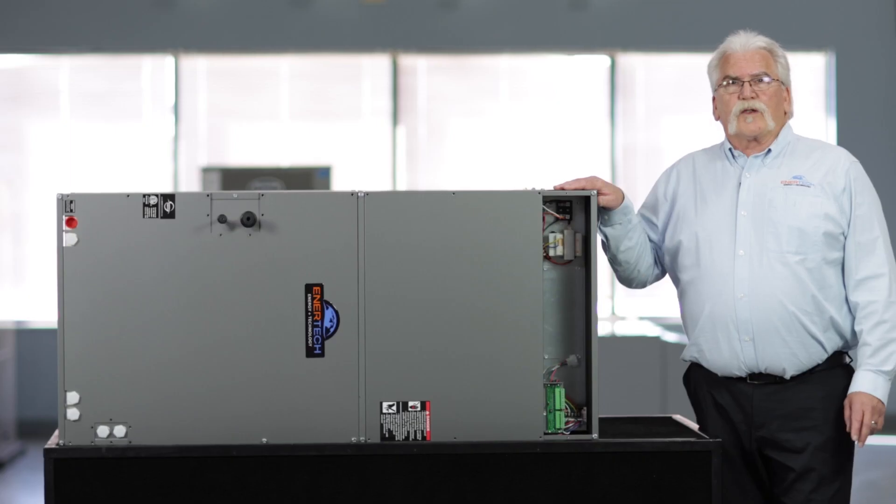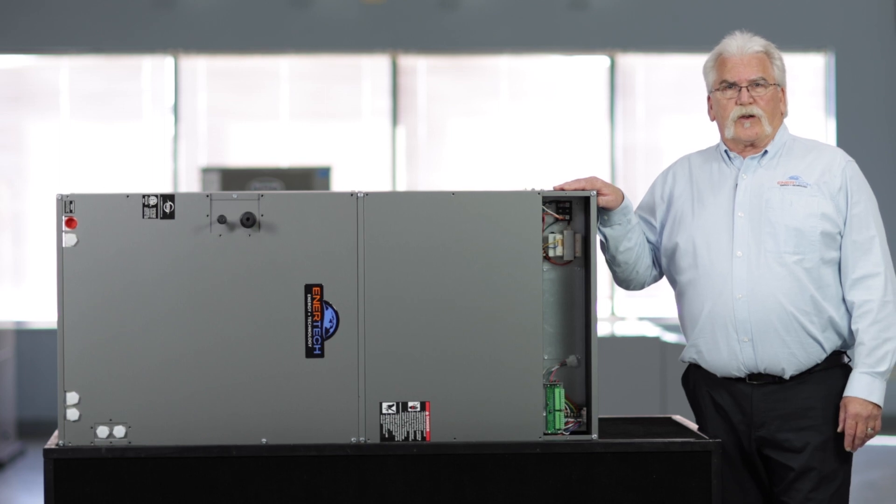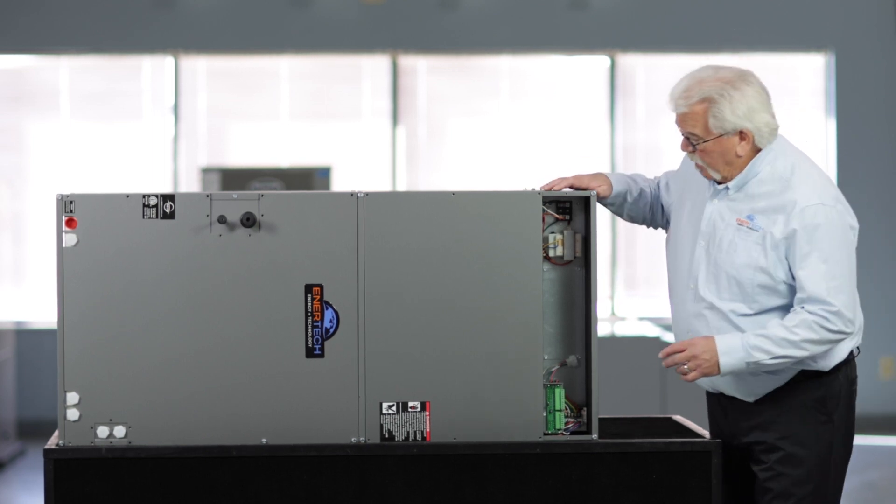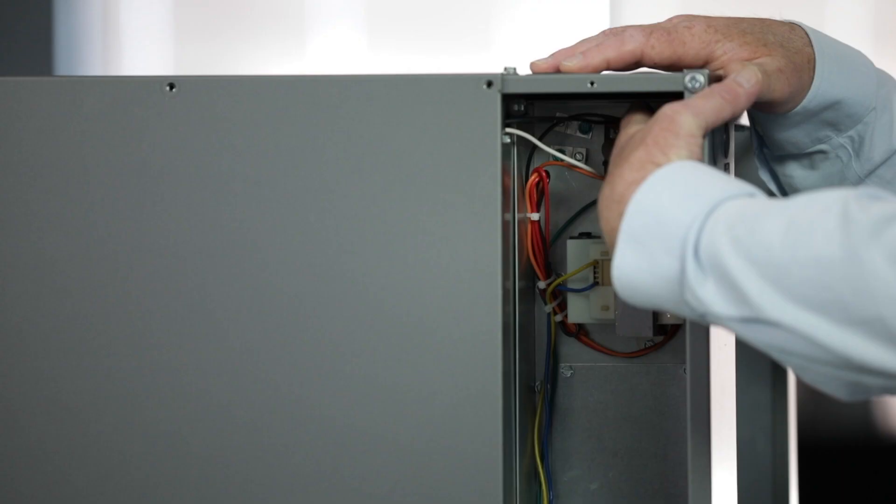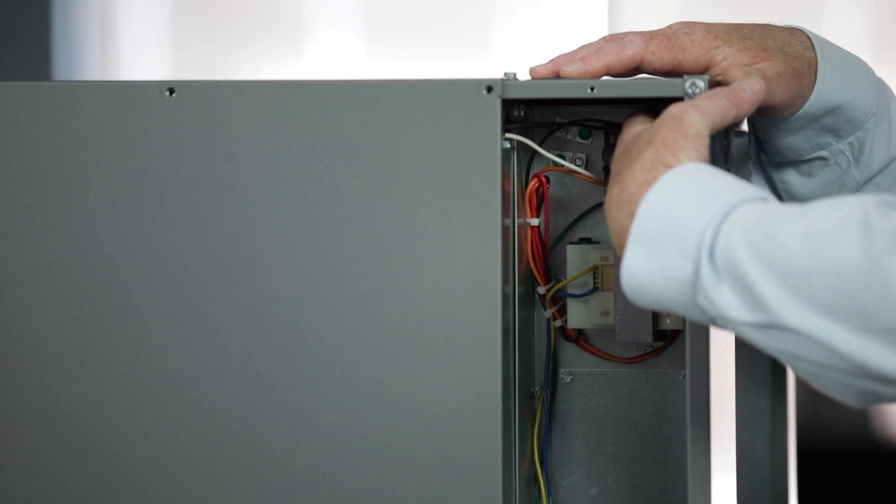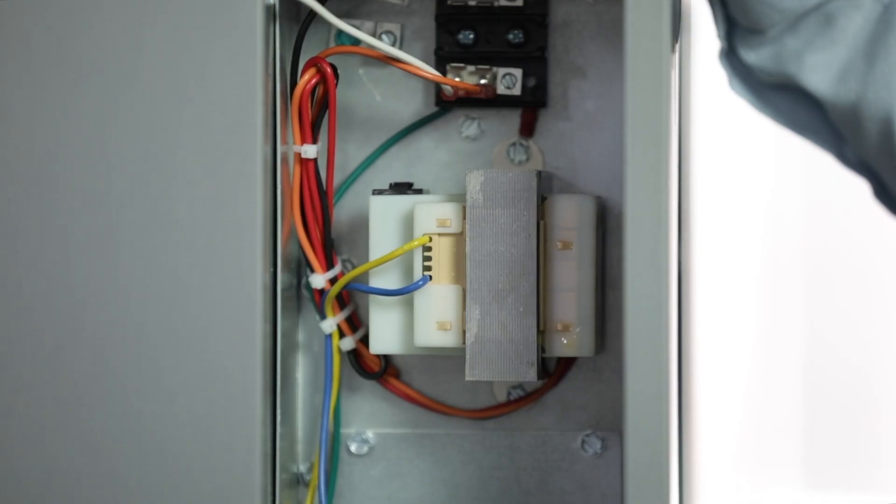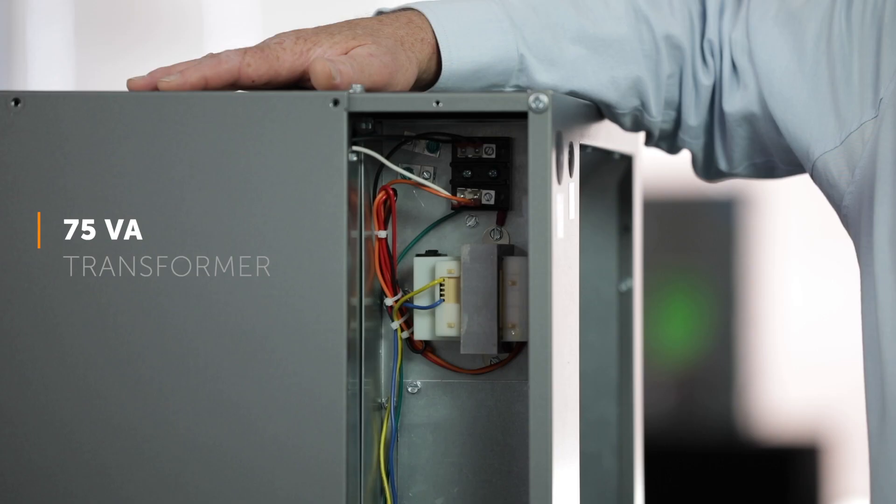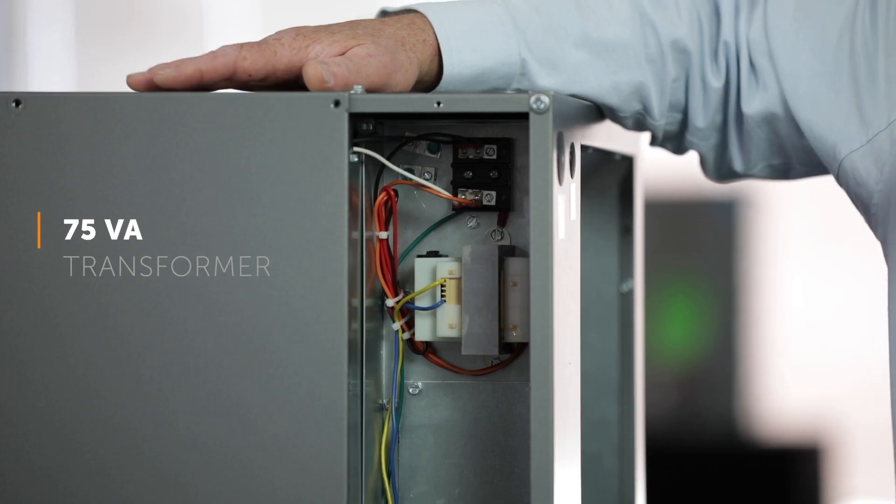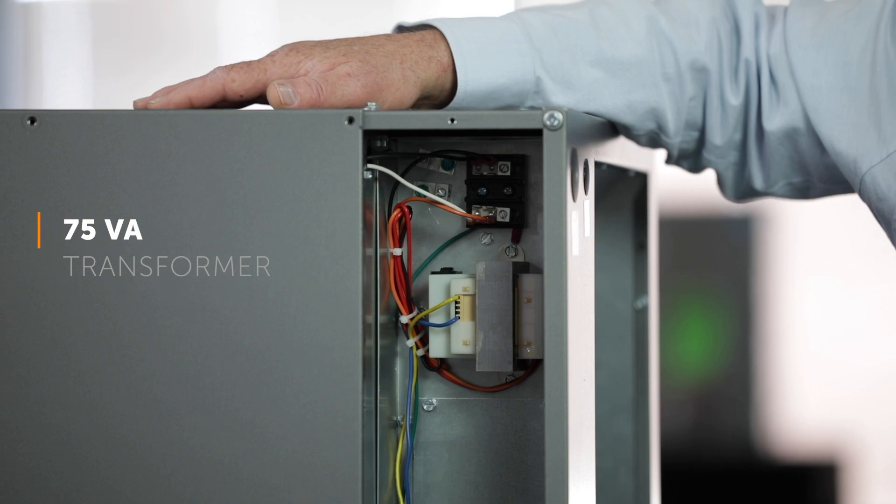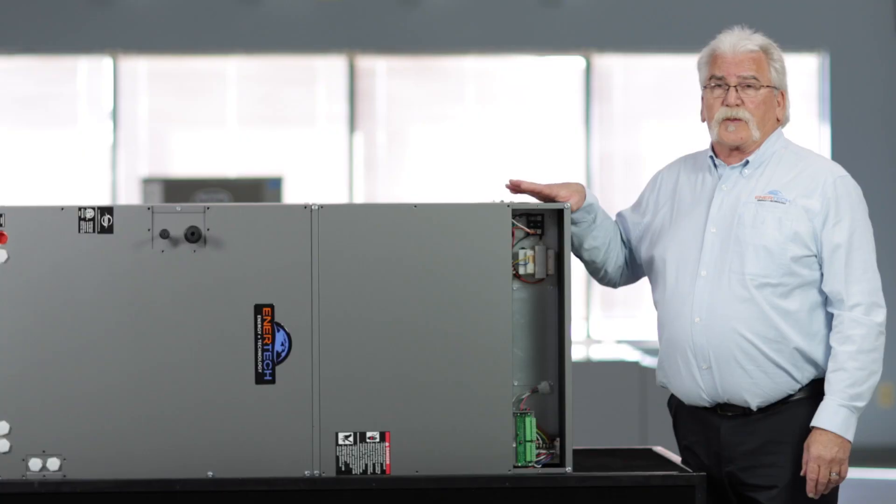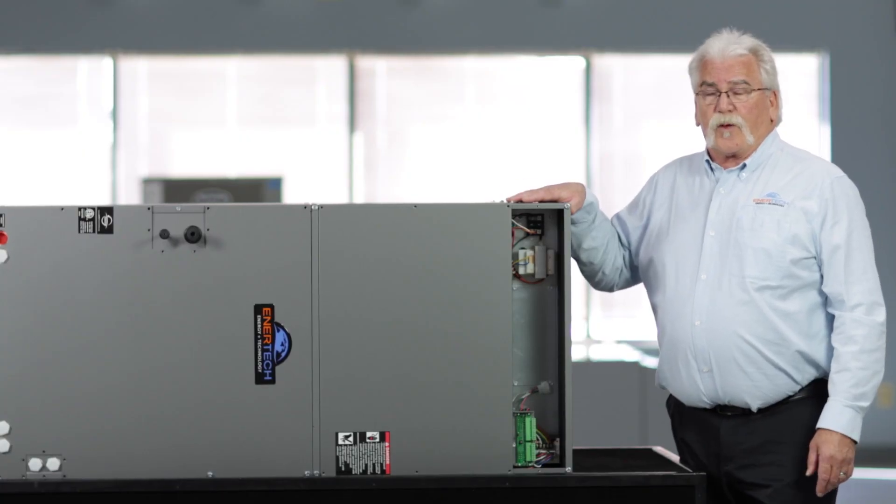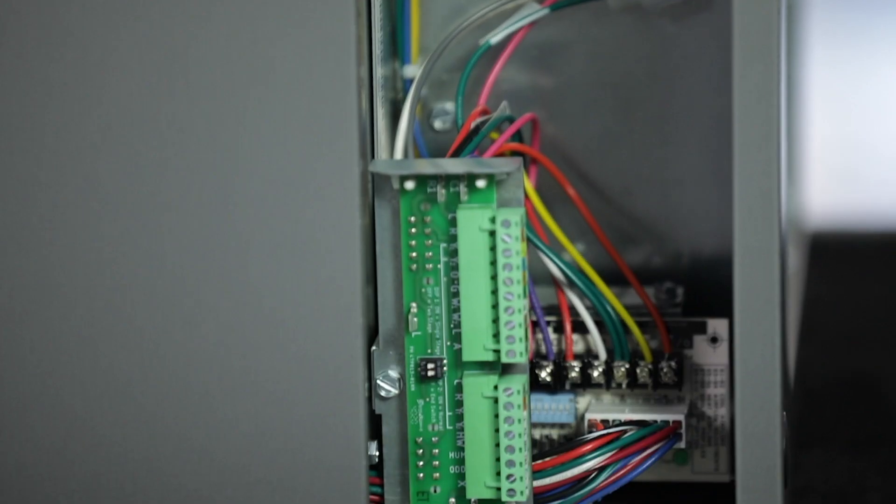For those of you familiar with Enertech products, wiring this unit will be a snap. The high voltage lugs are on the top. Your 75 VA transformer has enough power to power the air handler, the split system, and also a zoning system for your forced air.